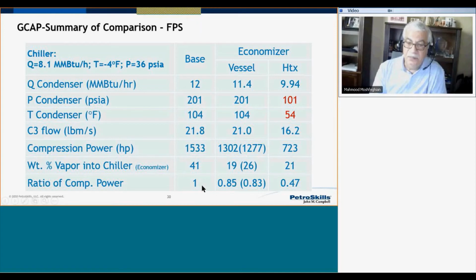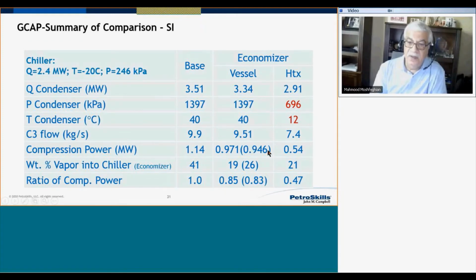And the power reduction, or how these two compare with the base case. If I divide 1302 by 1533, I end up with 85%. Sorry, the power requirement goes down to 85% of the base case. If I use this one here, the power requirement would be only 40% of the base case. So this is the most effective one. And I have a similar table for the SI units.